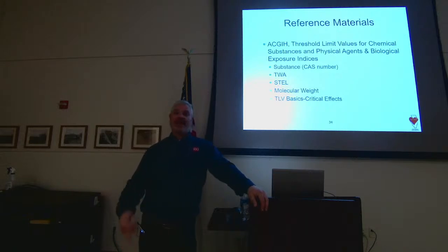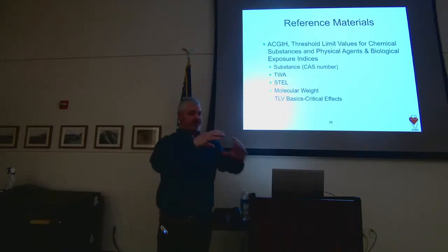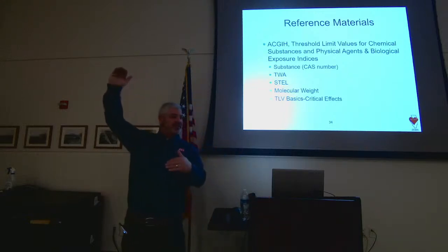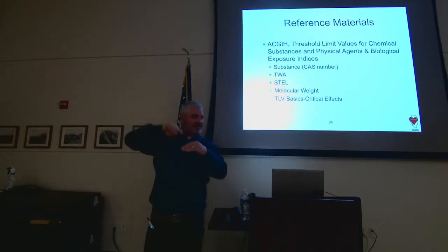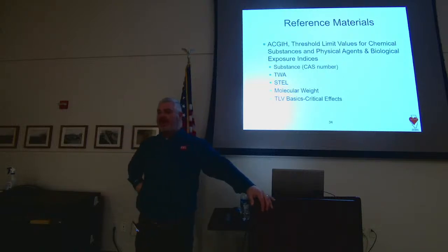Three days later, the guy calls. He says, hey, you just calibrated my instrument and I'm getting elevated levels—what did you do to my system? I calibrated it. I showed it zero air, 20.9, and a known concentration of bad air. I linearized that sensor. Everything passed. Well, this thing doesn't work, he says. I keep getting alarms, and if I get woken up at 2 o'clock in the morning again, I'm tearing the stuff out and putting in something new.